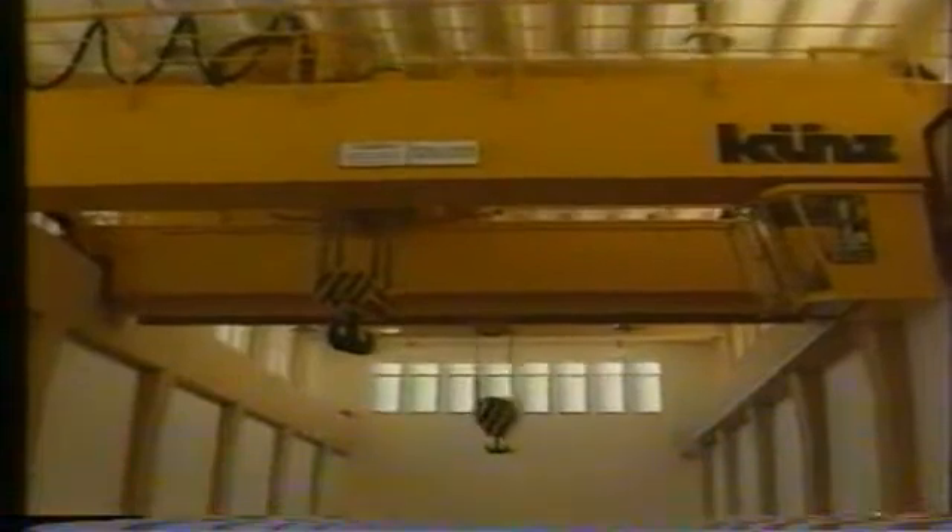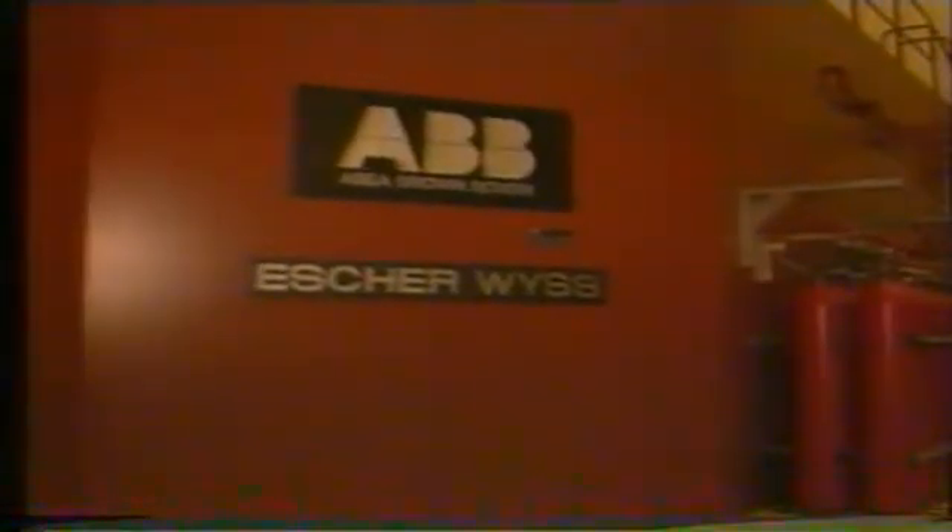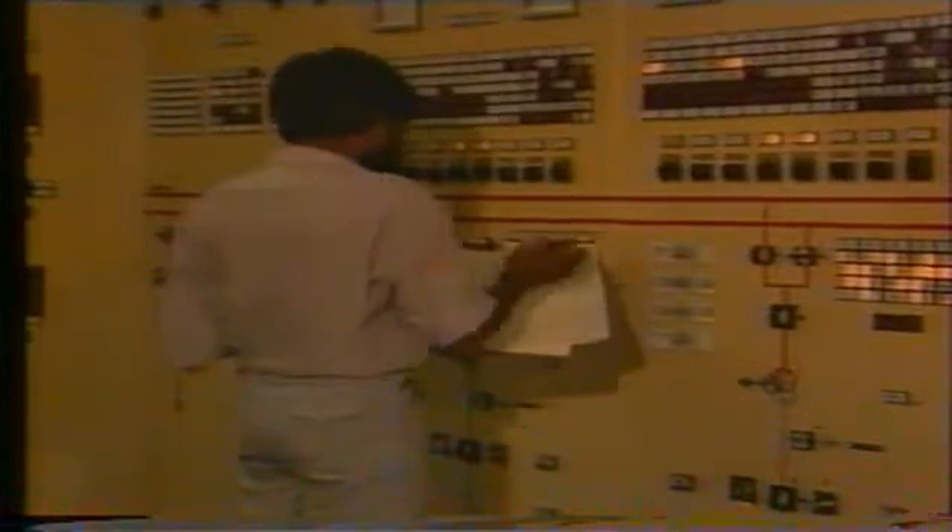Rantembe, which commenced commercial operation in 1990 after three years of construction, has a gross water head of 33 meters and is classified as a medium pressure power plant. The electricity produced by the generators at both Rantembe and Randenigala is fed into the national grid via a common switchyard at Rantembe and is operated by remote control from the national control center of the Ceylon Electricity Board.